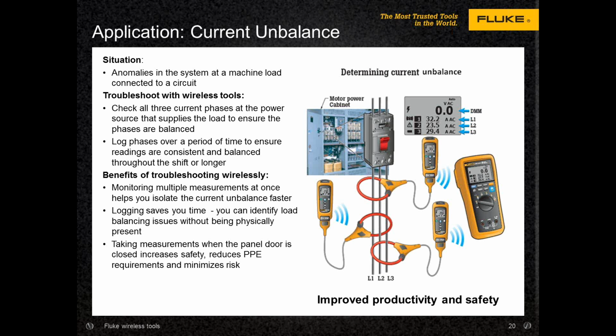the heck's going on. So now these flexible CTs, current transformers, right? A half an amp to 2,500 amps, is that correct? Yes. Okay, so pretty wide range for your ability. Well, there are two things going on with the flex clamps. One is you get very accurate readings. Those are essentially Rogowski coils. You get very accurate readings from the low end to the high end. That's something you don't normally get with a conventional current clamp that's got a rectangular jaw.